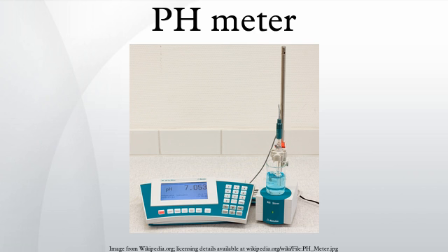The pH meter has one control to set the meter reading equal to the value of the first standard buffer and a second control which is used to adjust the meter reading to the value of the second buffer. A third control allows the temperature to be set. Standard buffer sachets, which can be obtained from a variety of suppliers, usually state how the buffer value changes with temperature. For more precise measurements, a 3-buffer solution calibration is preferred.